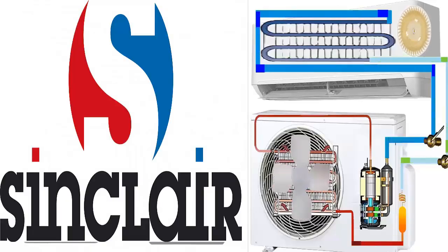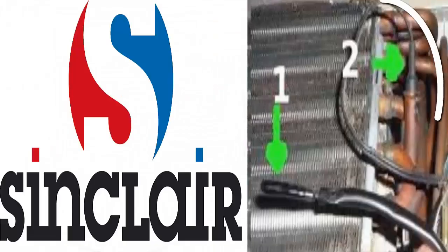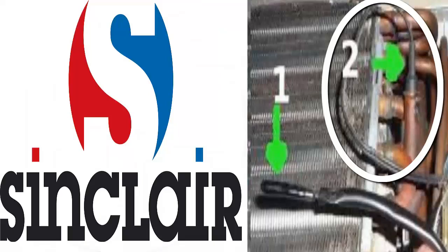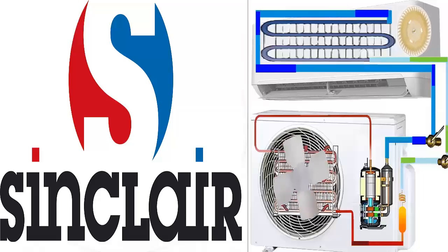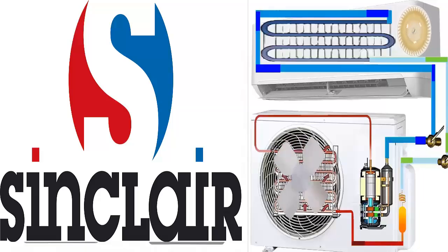Code F2 indicates problems with the indoor coil sensor being open or short-circuited. This sensor measures the refrigerant's temperature inside the indoor unit's heat exchanger, mainly to prevent coil freezing in cooling mode.